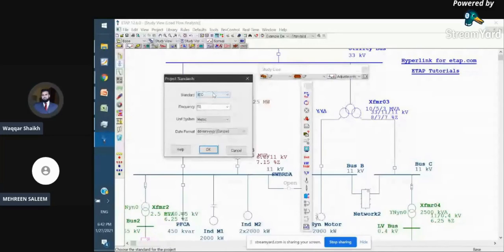Now the other option is the frequency. Frequency has a very important role in some of the studies. Let's take an example. For any conductor, we have resistance offered by the conductor or the reactance offered by the conductor. And the reactance is a function of frequency, for example inductive reactance, 2 pi f L. So by changing the frequency from 50 to 60 hertz, we are changing the impedance of a cable. So impedance is a function of frequency in the end. By not selecting the right frequency, ETAP software will not be able to bring the correct results.